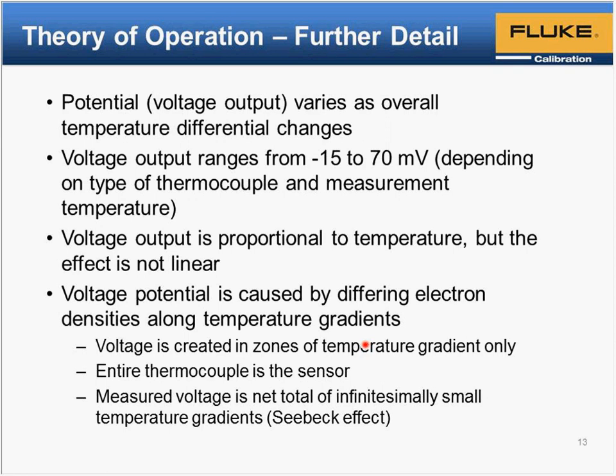Thermocouple wire is never perfectly consistent, so the other thing to consider is that the entire length of the thermocouple is the sensor. So all of the thermocouple wire is involved in producing a voltage for you to measure. The majority of the voltage is generated in the gradient region. Technically, there are tiny little gradient regions throughout the entire length of the thermocouple. Like if the thermocouple passes through a typical room, it's around 23 degrees, but if you zoom in to micro levels, you will see that there are, this is always a hard word to say, infinitesimally small temperature gradients throughout the length of the wire. Now, true, as the wire passes through a room, the temperature gradients are fairly small, but they're there. They are there, and they are contributors to the overall circuit.